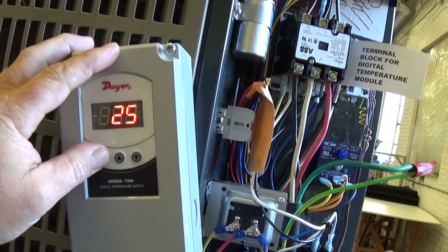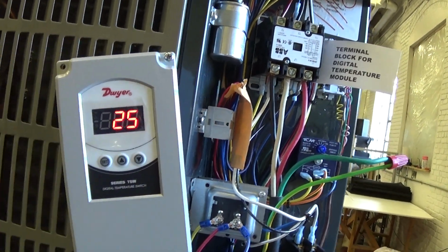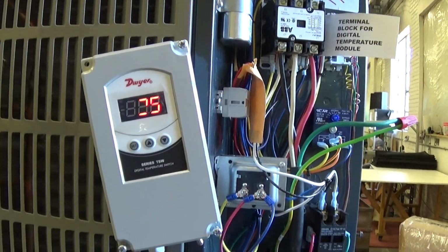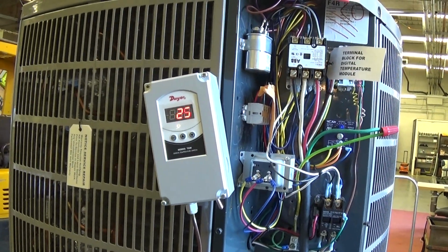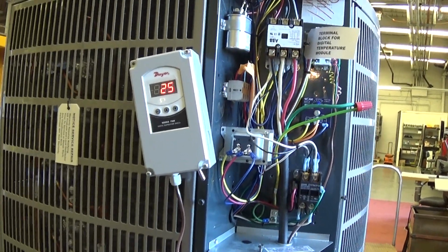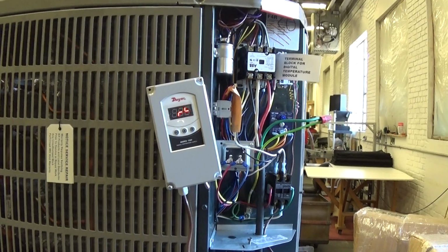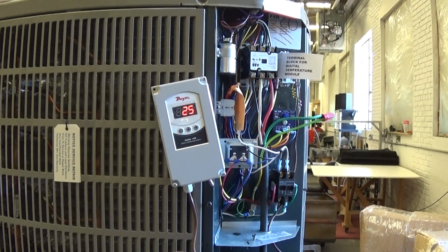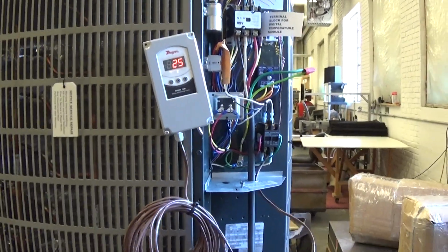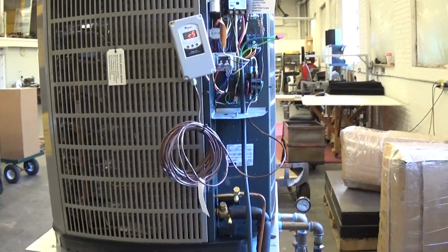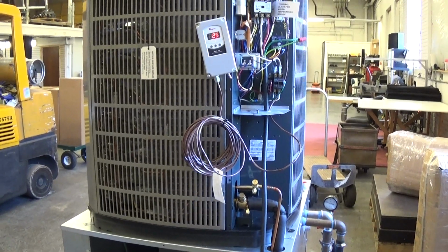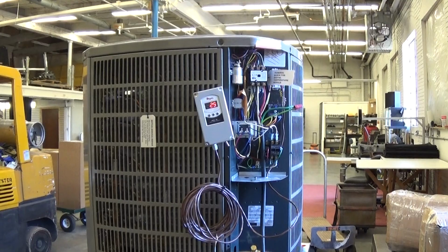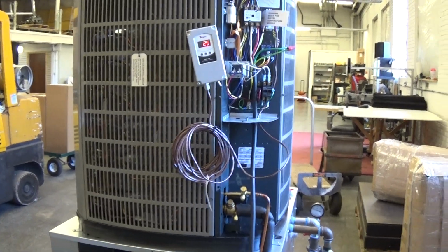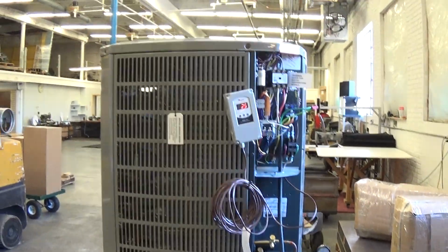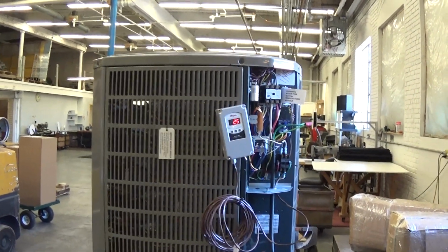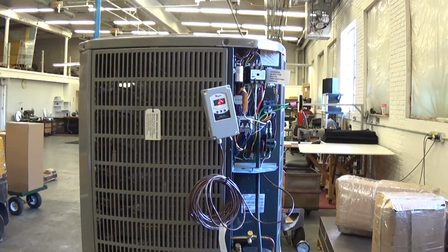And press set again. That just goes back to 25, but it's going to default back to what the process temperature is, and there'll be a little bit of a delay before the compressor kicks back on and starts cooling. This specific unit, because it's going to run basic water out in the field with very little glycol mixture, if any, is going to leave the factory with a 44 Fahrenheit lowest set point. But for glycol chillers running lower temp, it will be set at 25 Fahrenheit.